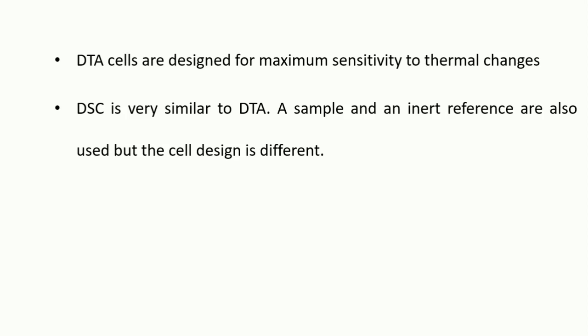DSC is quite similar to DTA. A sample and an inert reference are also used, but the cell design is different. In some DSC cells, the sample and reference are maintained at the same temperature during heating, and the extra heat input to the sample or to the reference, if the sample undergoes an exothermic change, required in order to maintain this balance is measured.